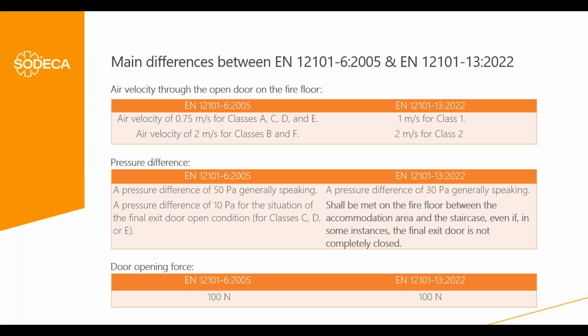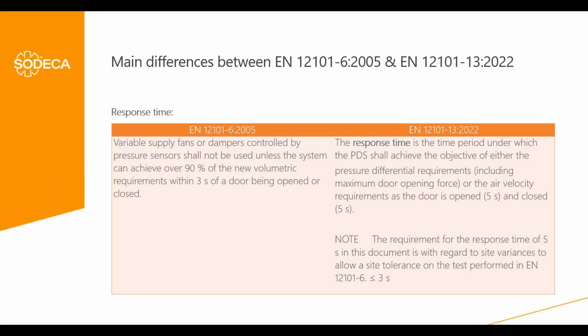So if we cannot ensure that this door will be completely closed, we have to consider the potential leakage, or the potential opening on that final exit, in our calculation. About the door opening force, it is the same, 100 Newton, there was no such change.